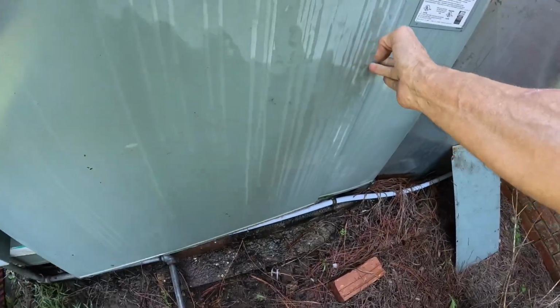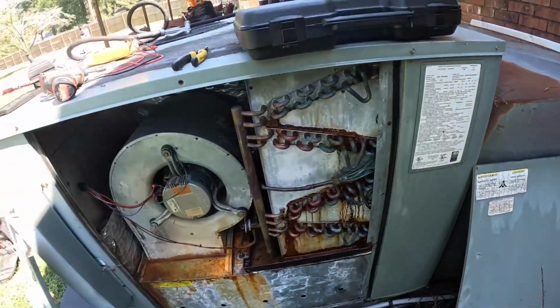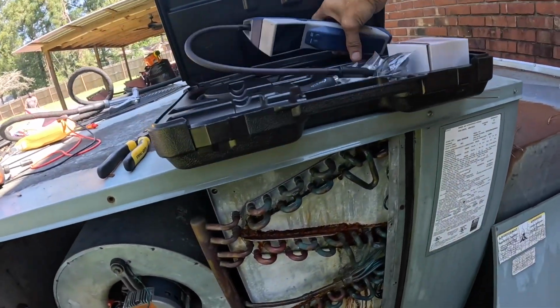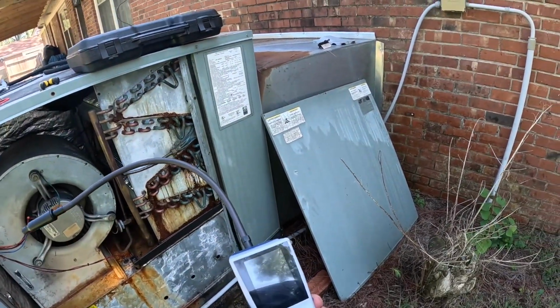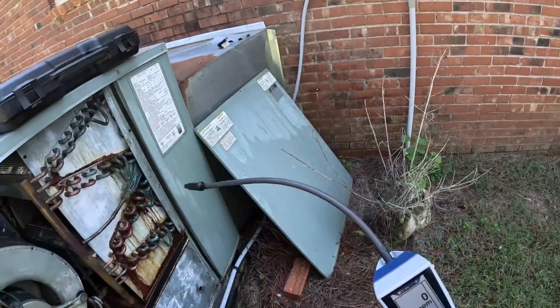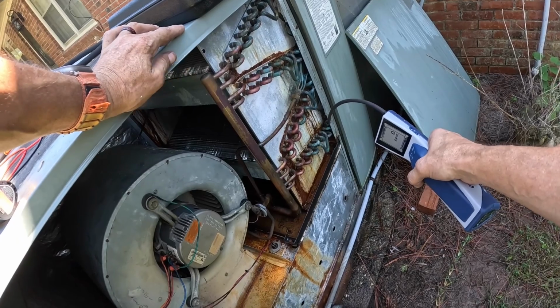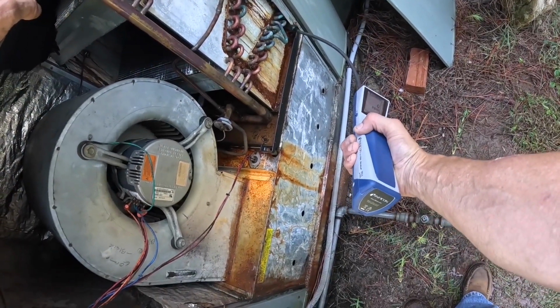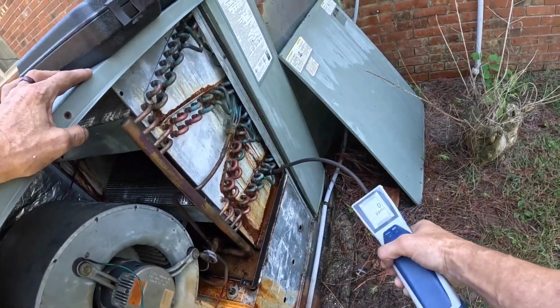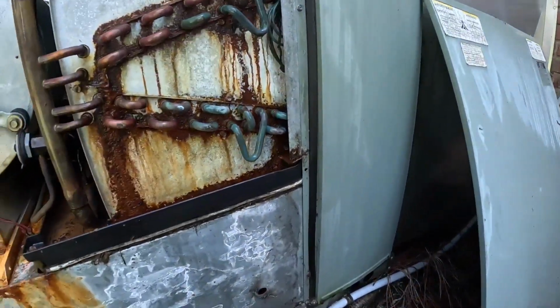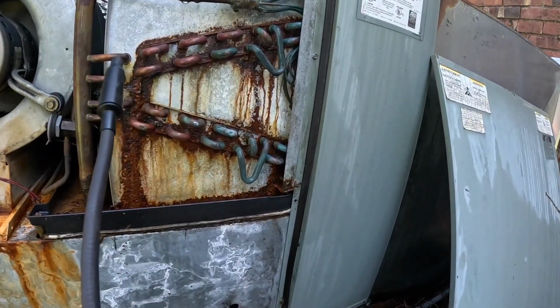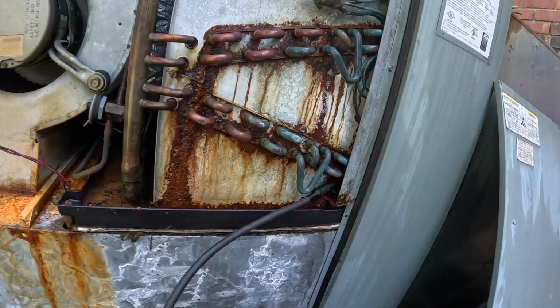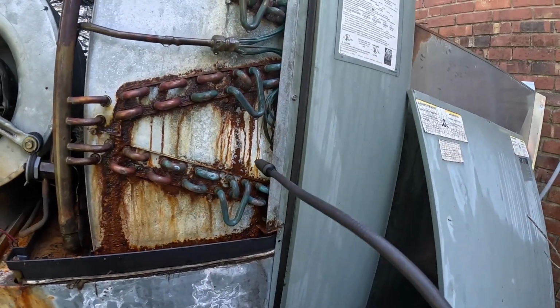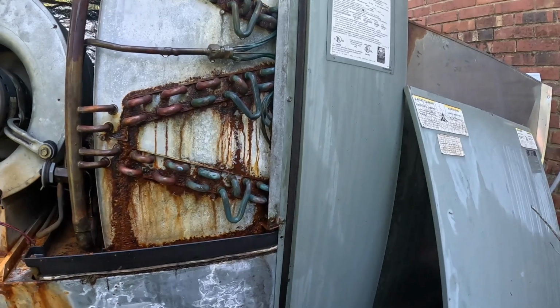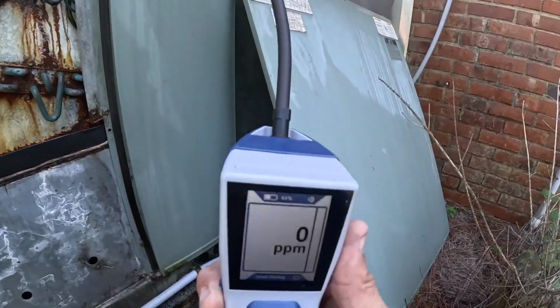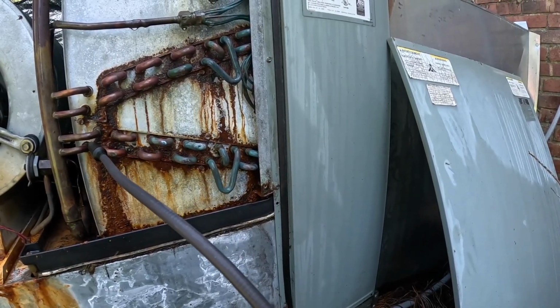Start over here. I'm on parts per million. It seems like with the older leak detectors, this is an infrared, but if I had one of the heated diodes, if it was leaking, you would almost always find it right here. But I'm finding I have better success if I search behind the tube sheet here with this one.